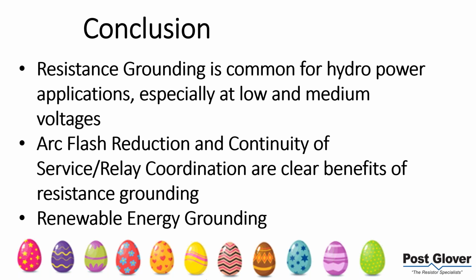So the conclusion is that resistance grounding is common for hydropower applications. We do them a lot, like I mentioned, especially at low and medium voltages, more so medium, but also low. Arc flash reduction, continuity of service, and relay coordination are clear benefits of resistance grounding. That's really why you're going to want to be using it. If those aren't something you are interested in or not as important to you, especially for your renewable application, you probably won't want to use it. That's usually why a lot of the main applications with process or downtime concerns are high resistance ground applications. Then low resistance ground, once again, is coordination, et cetera.